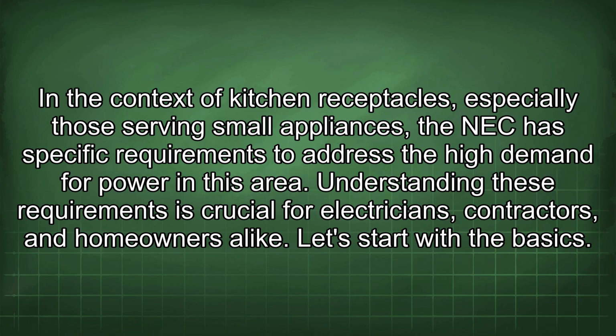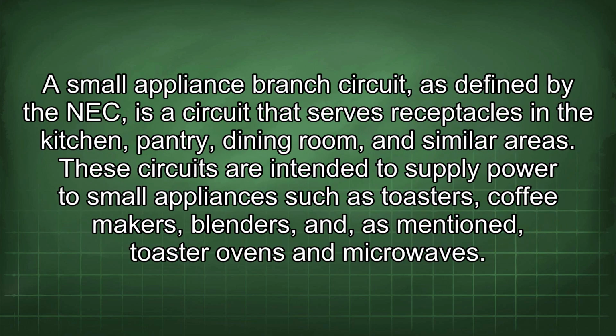In the context of kitchen receptacles, especially those serving small appliances, the NEC has specific requirements to address the high demand for power in this area. Understanding these requirements is crucial for electricians, contractors, and homeowners alike. Let's start with the basics. A small appliance branch circuit, as defined by the NEC, is a circuit that serves receptacles in the kitchen, pantry, dining room, and similar areas.